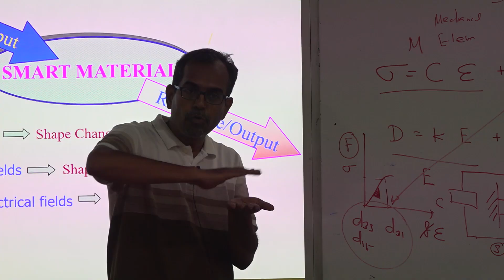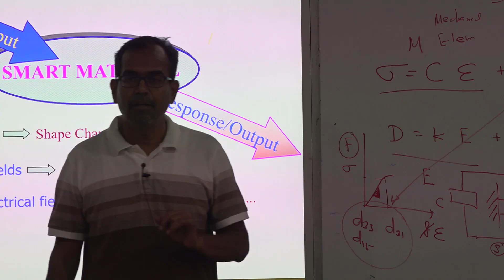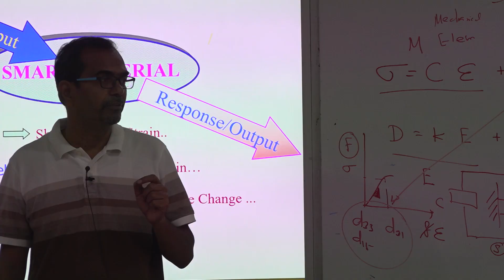There are piezo test meters available, or you have to identify the properties yourself. See what is happening generally in mechanical materials: we do not want to operate near resonance, because when you operate anything near resonance, it will fail. But for this kind of smart material, in order to get the material properties, we operate near the resonance and anti-resonance frequencies, and we get the frequencies from there using an impedance analyzer. Standards are available to do the theoretical calculations, and this will give you all the material properties you want. I mean C, D and kappa: using the impedance analyzer we measure some frequency information, and from that we calculate them.